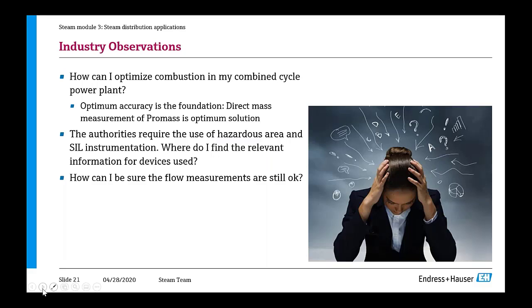So we come back to the industry observations. The first one was, how can I optimize the combustion in my combined cycle power plant? So the optimum accuracy is always the foundation. If you want to know how efficient you really are, then you need good measurements, of course. And the best accuracy you can get is using the Promass for the natural gas measurement.